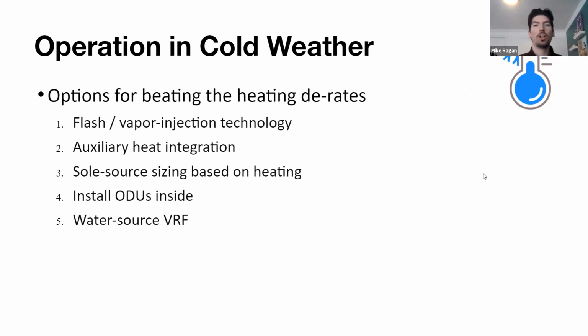So we're going to talk now about the various ways that we use heat pumps to efficiently design systems to avoid any of those heating derates. Again, as it gets colder outside, the performance of the system is going to slowly start to diminish. So here are the methods that we use to mitigate that, to make sure that even on the worst case scenario day, if you have a VRF system as your sole source of heat, we'll design it in such a way that you get all the heat you need in the worst case scenario.